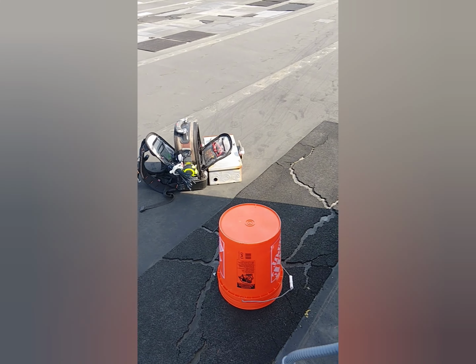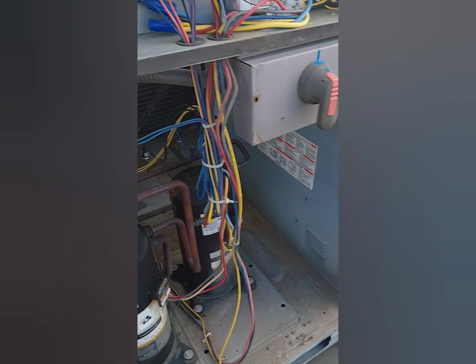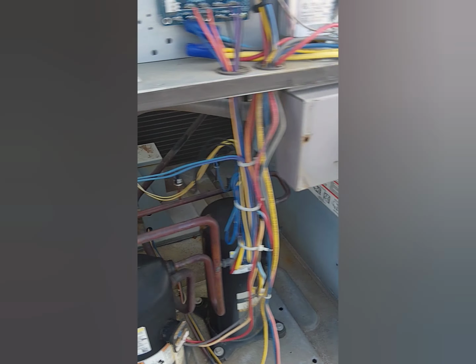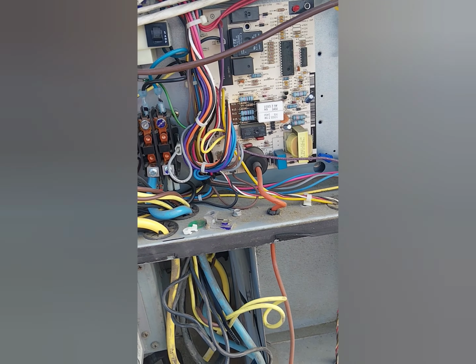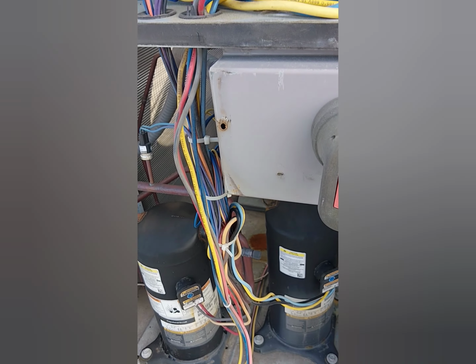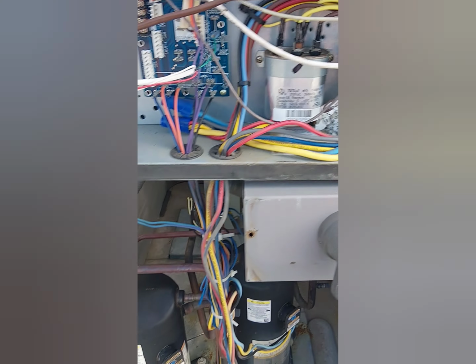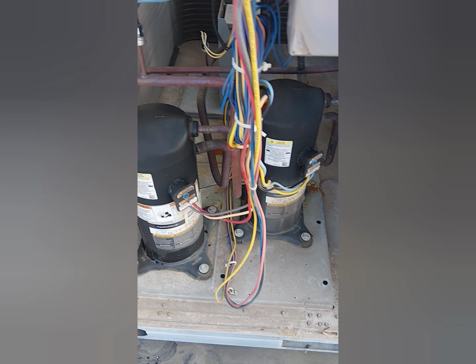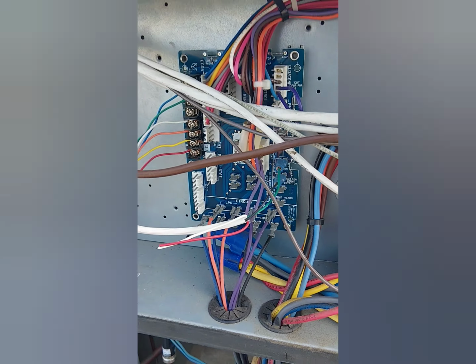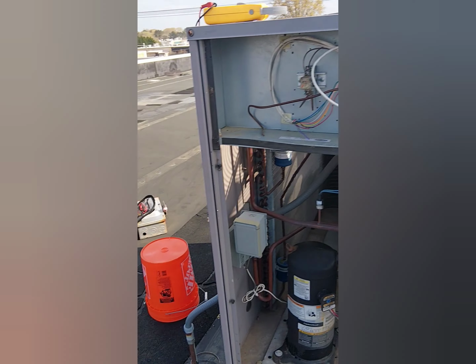Yeah man, so, bloopers, but yeah, we good. Both disconnects, the old disconnect is right here as you can see. New disconnect is in. Compressors, everything working, man. I did ohm out everything, checked the windings on the compressor, ohmed out the contactors, checked the capacitor. Yeah man, we good, we're gonna clean up and get out of here.